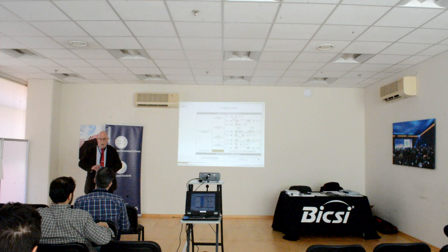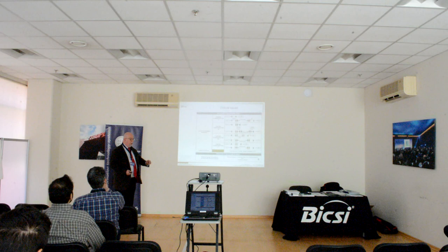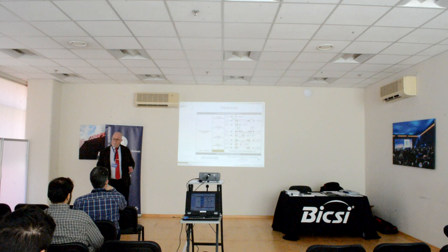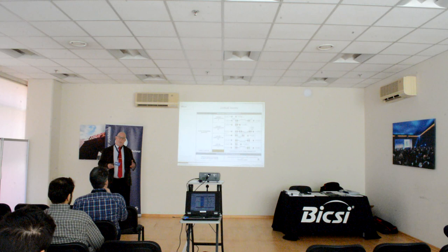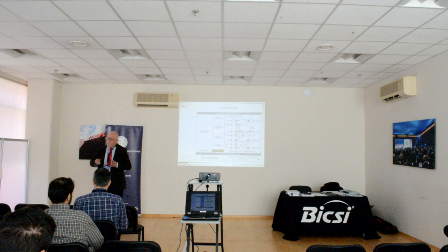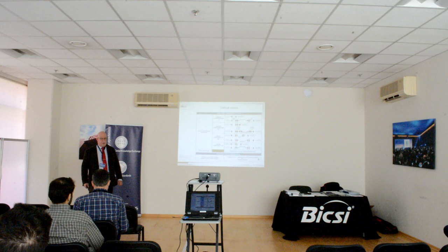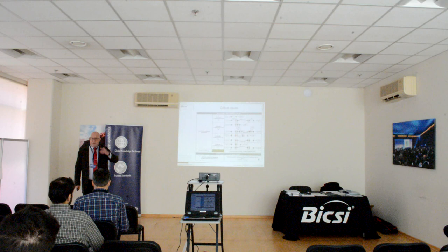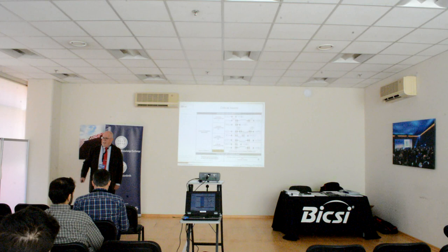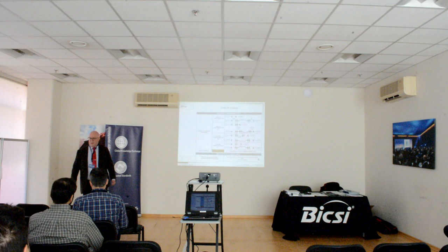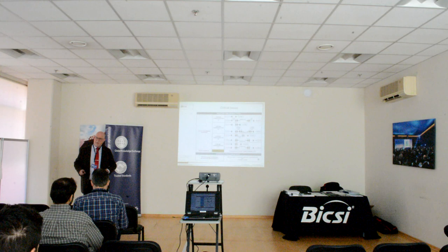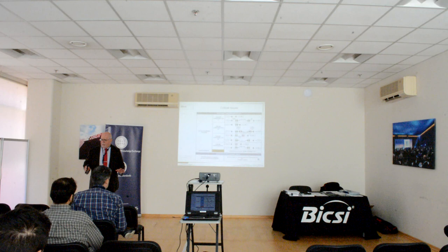So now if you follow the standards and you're measuring against a limit of 2.8 dBs using reference cords, first of all you have to change your limit, maybe down to 1.9 dBs for the same thing, because you're using reference cords to test it with, which are a better performance product, and then you'll probably get a result of 1.6 dBs. And the customer says, wow, that's fantastic, my limit was 2.8 dBs, I've now got performance of 1.6 dBs. I'll just go and buy some cords from the local supplier, he puts them in, measures it again, finds it's 2.7 dBs. Well, you told me it was 1.6 dBs. Yes, but we're using reference cords. Well, shouldn't I be using reference? You don't want to have this confusion.